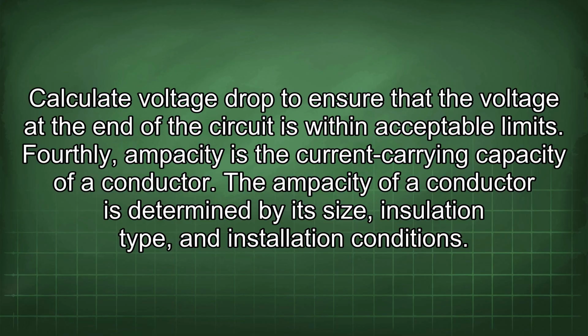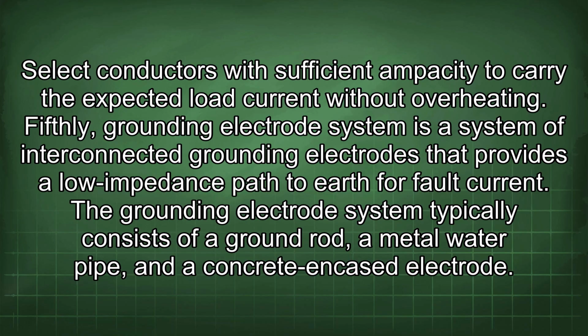Fourthly, ampacity is the current carrying capacity of a conductor. The ampacity of a conductor is determined by its size, insulation type, and installation conditions. Select conductors with sufficient ampacity to carry the expected load current without overheating.